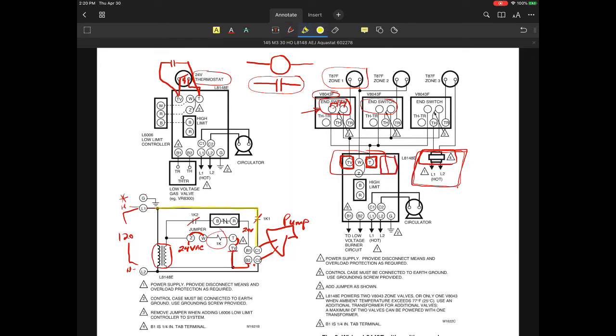I've seen these applications where guys have installed these in the field, and this transformer was fighting against the transformer that was internal in this system, and that created a problem. So I generally try to isolate those and do them differently, so that I'm not using both of these two. I'm not using the transformer here, and a separate one here, and trying to tie them together. That's really kind of dangerous to do. I would highly recommend not doing that. It also makes it a lot easier to troubleshoot these.